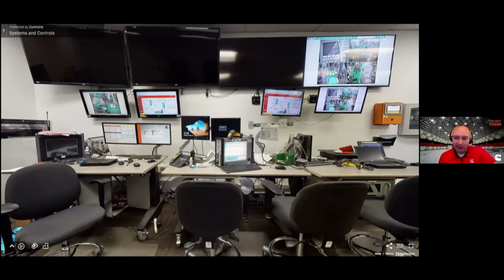We've got load bank control, which would be on this screen here and here. We can tap right into the ECM, the engine computer, or onto the generator computer, done through this one. And we've got high-speed data acquisition that allows us to take frequency and voltage traces at a 10,000 hertz sample rate, based on the customer's needs.